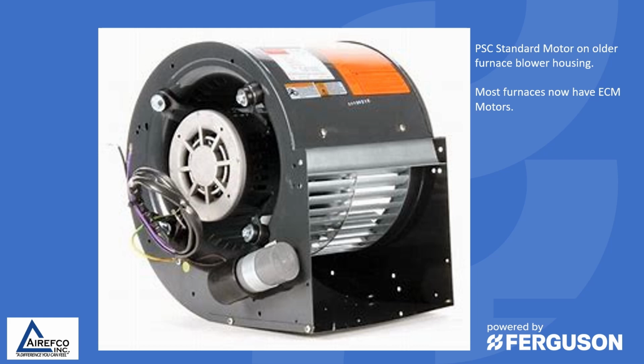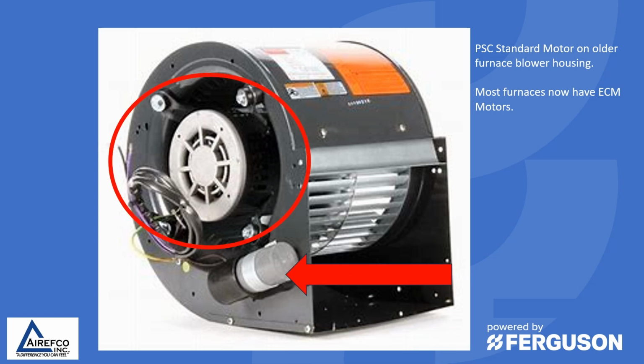Let's talk about furnace blower motors and blower wheels. Most of your older furnaces had the standard PSC motors, and they had a run capacitor along with them. And those have kind of gone away. I mean, you'll still see them when you do maintenance work or troubleshooting on older furnaces. But most furnaces now have ECM motors.